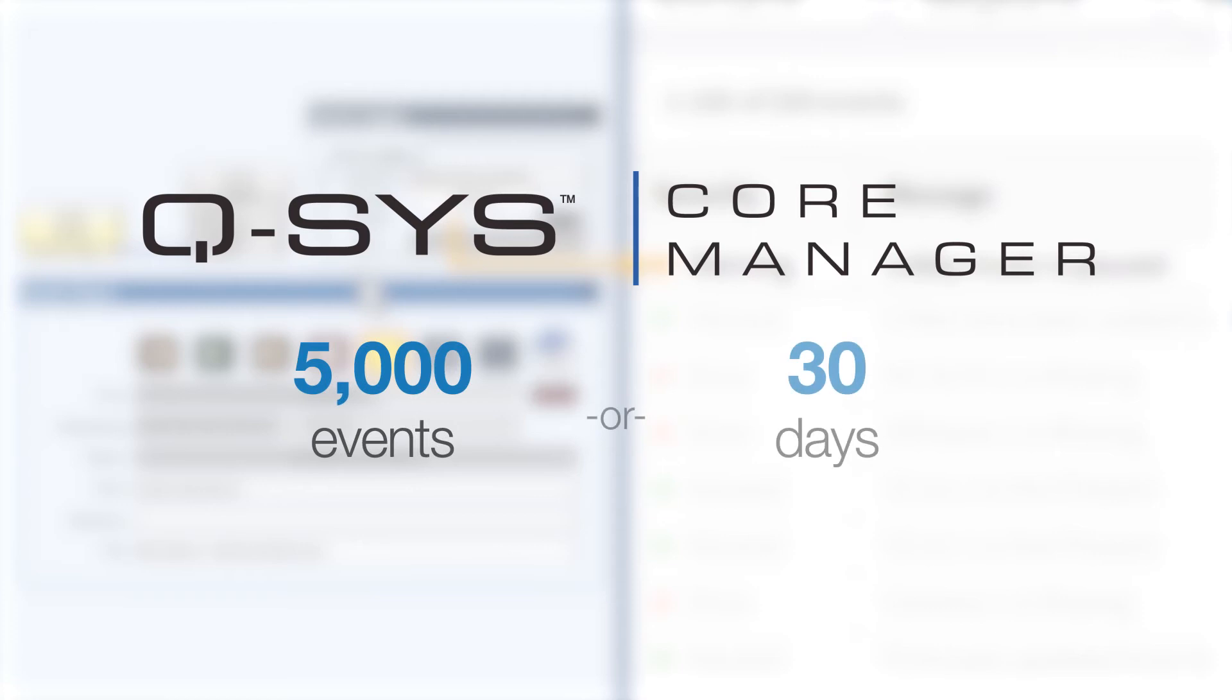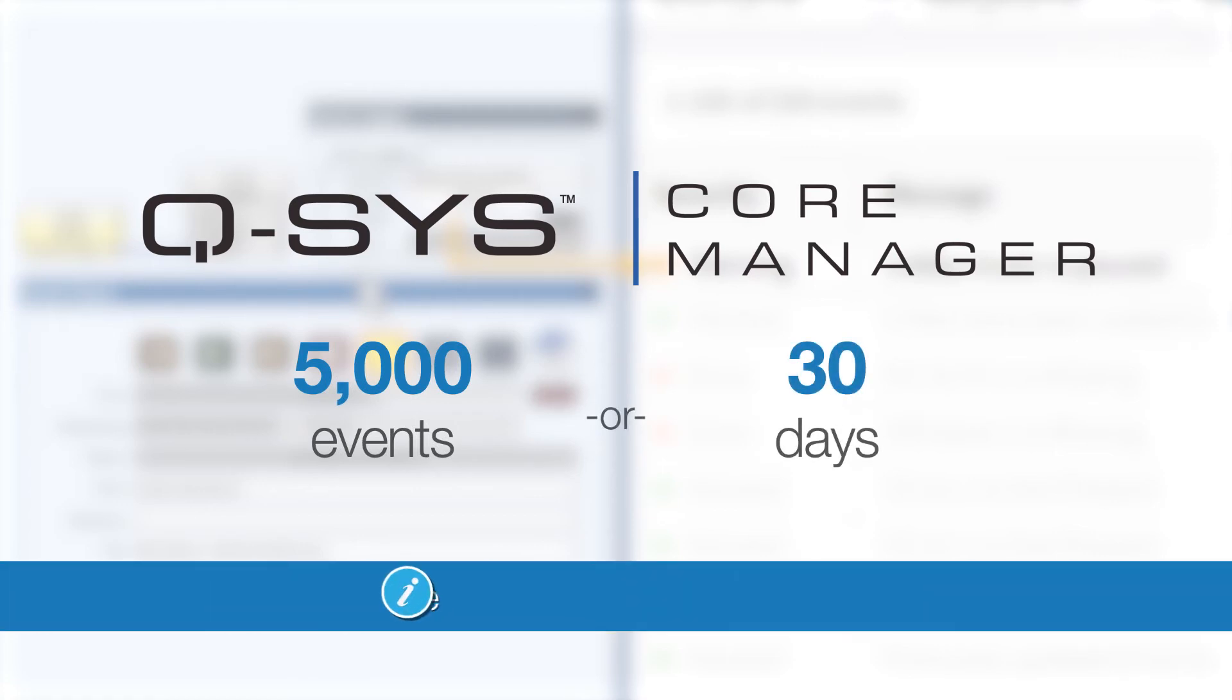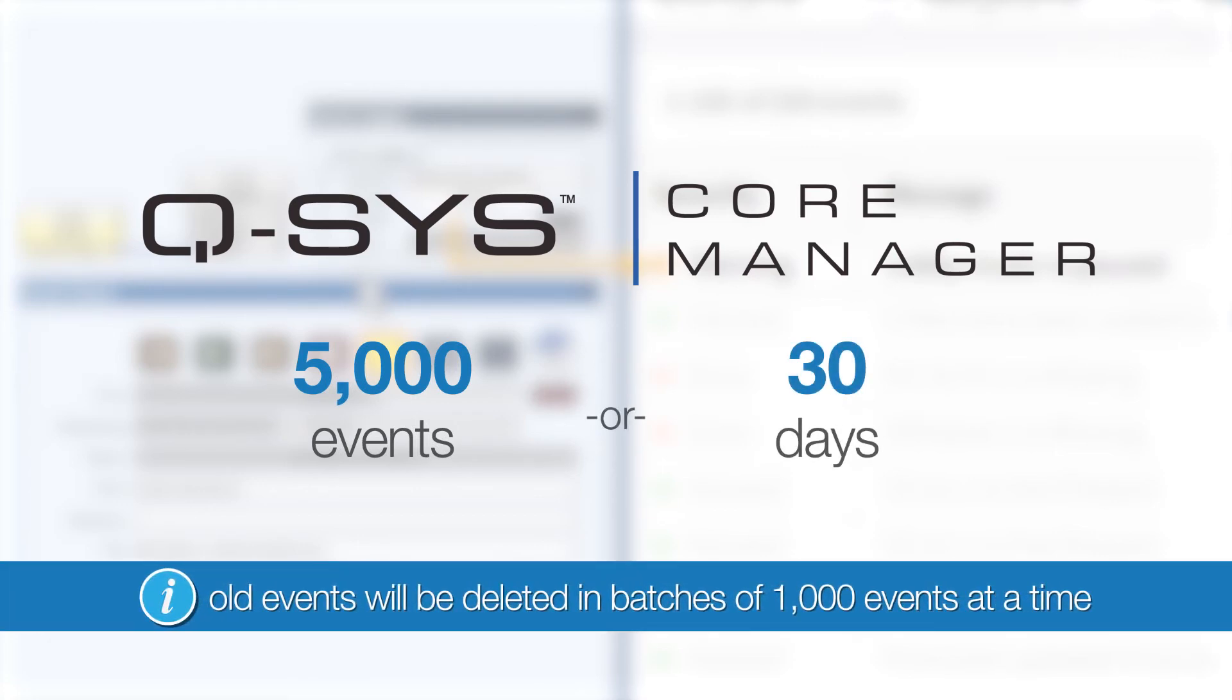Core Manager will store up to 5,000 events, or 30 days' worth of activity, whichever one comes first. After this, the oldest events will be deleted in batches of 1,000 events at a time, so technically it could store up to 6,000 events before this deletion.